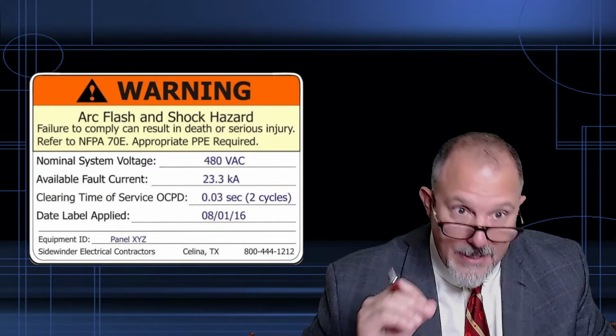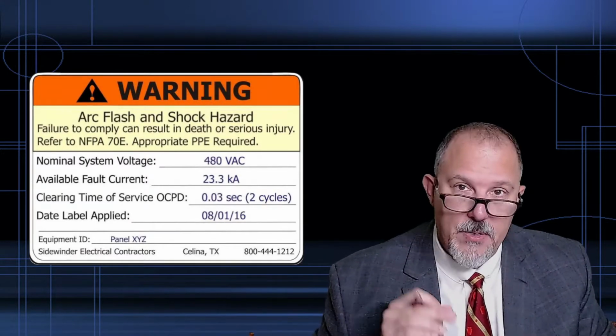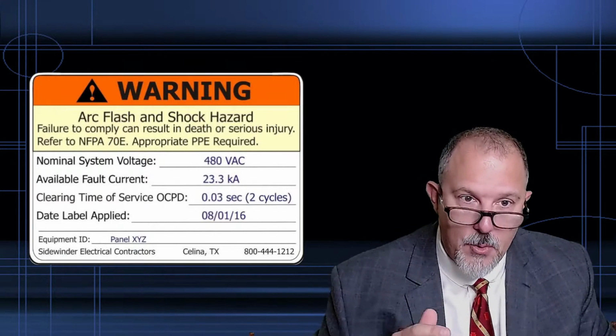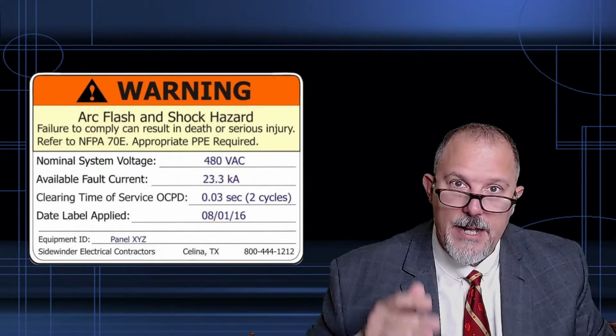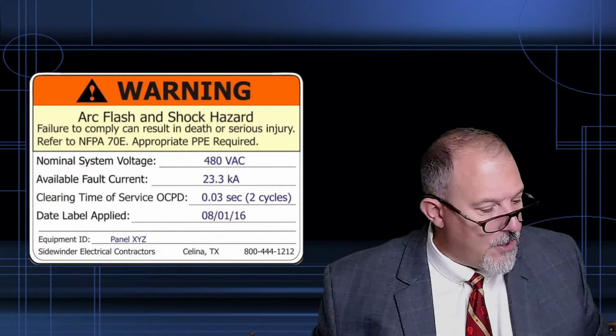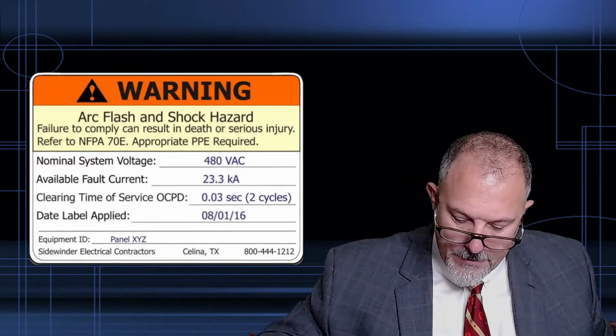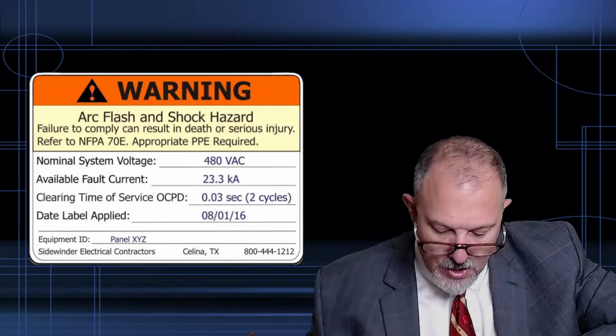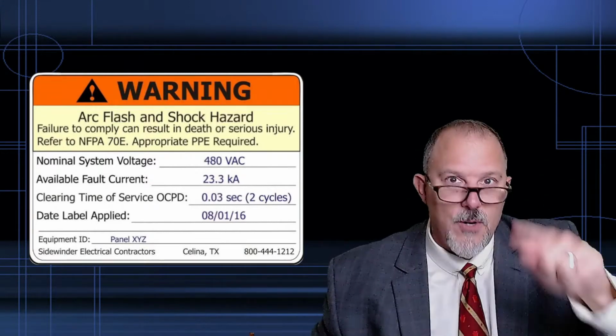I remember it distinctly. And they said we can't put maximum available fault current. We have to put just available fault current, and it will be the actual current at the service, at this equipment, at the service equipment. And the service equipment is where this label is required.